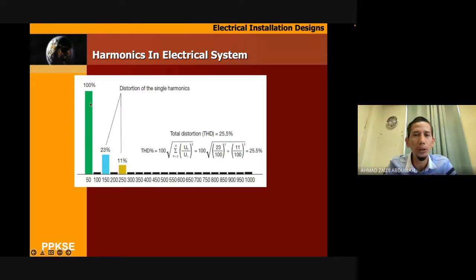Let's say we have a signal with 100% fundamental. In the third and fifth, we can see there is distortion, for example at least 23% and 11%. That is an example. For the total distortion, we can use this formula, if we pick only two levels of harmonic distortion, which are the third and fifth.